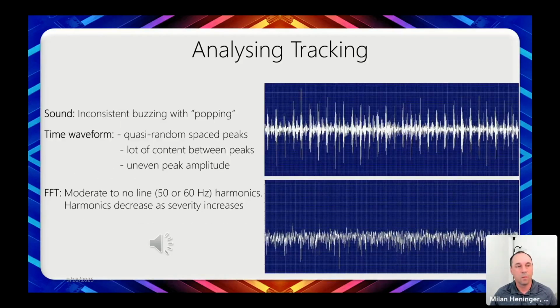So when we analyze tracking, we are now getting a more inconsistent buzz with some popping sounds. We get some quasi-random peaks. Lots of content starts to come up between the peaks, and we tend to have a more uneven peak amplitude. You will sometimes have some harmonics show up. Usually what I've seen is that the harmonics decrease as the severity of the tracking increases. All right, so as we move from tracking towards arcing, the harmonic content will continue to diminish.